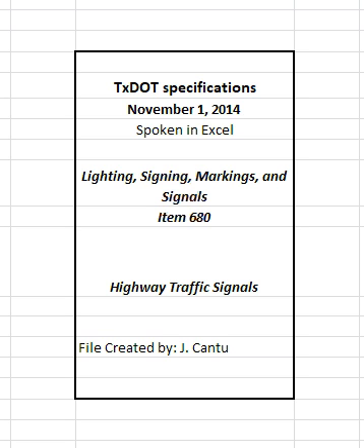Remove abandoned concrete foundations, including steel, to a point 2 feet below final grade. Backfill holes with material equal in composition and density to the surrounding area. Replace surfacing material with similar material to an equivalent condition. Accept ownership and dispose of unsalvageable materials in accordance with federal, state, and local regulations.